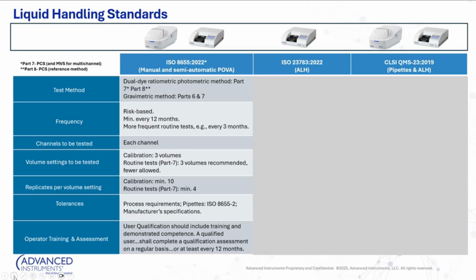And so ISO 8655 really gives you some prescriptive methods, specifically in the reference measurement standards, that are very, very detailed. But then Part 7 becomes a little bit less stringent, and it's a little bit more applicable for your everyday lab. We're going to talk about that. But the nice thing about it is that you can find some autonomy, and then you can also find something that's very prescriptive and very detailed that you should follow. With regards to channels, ISO 8655 indicates every channel should be tested.